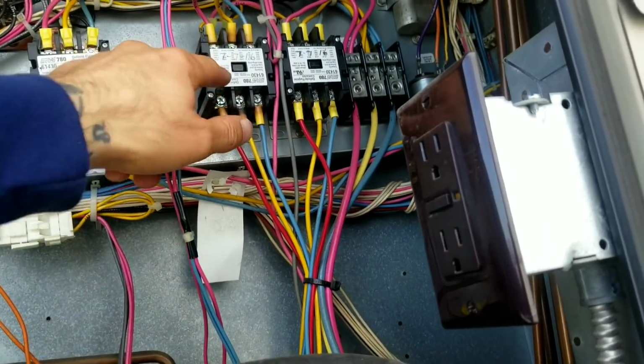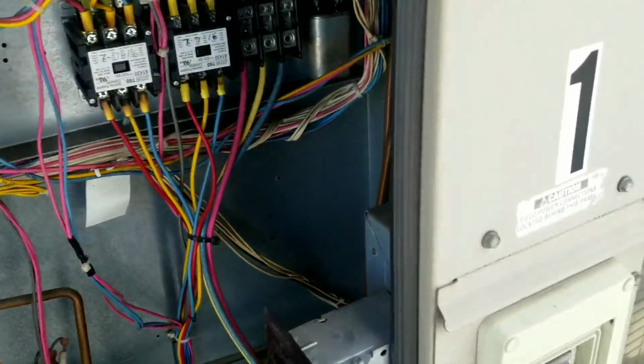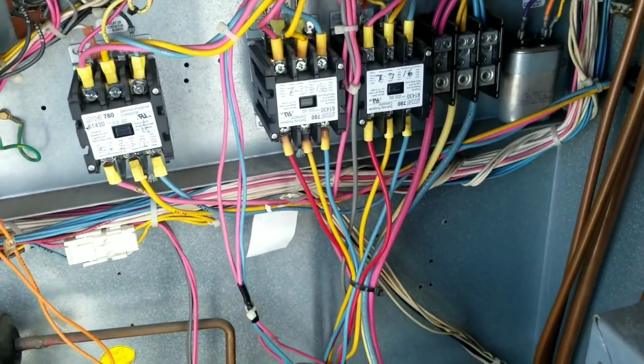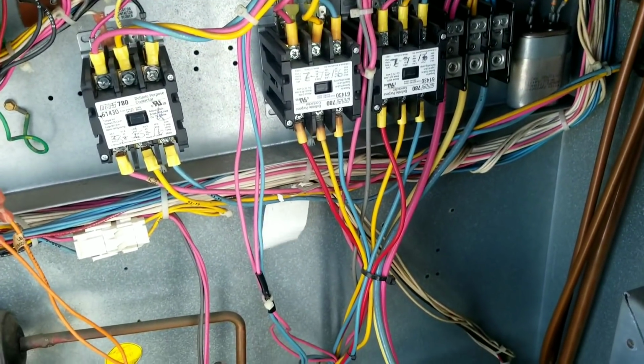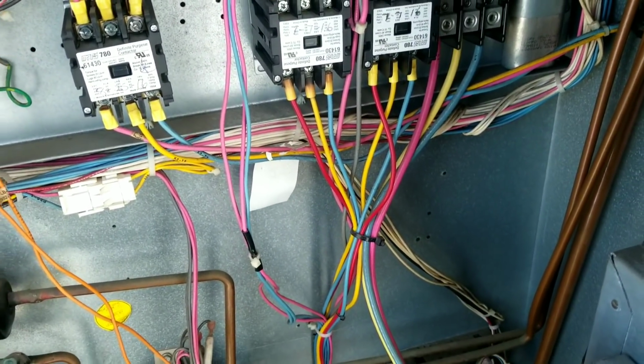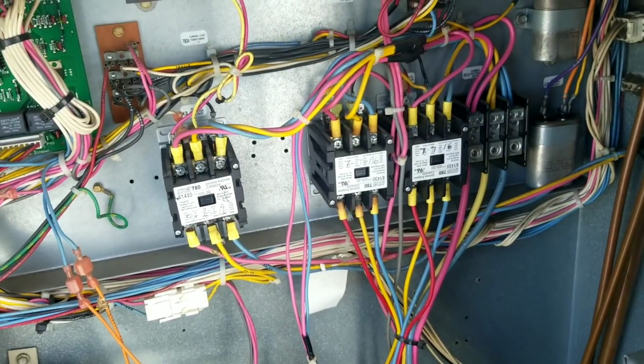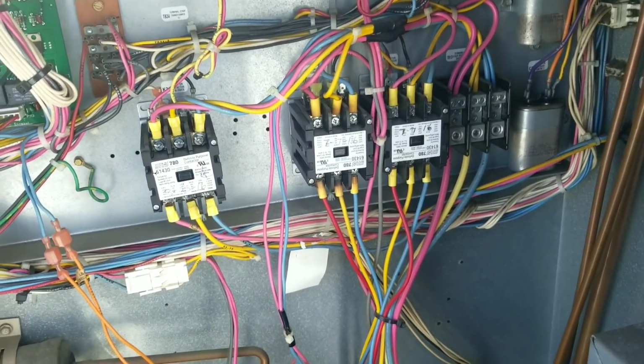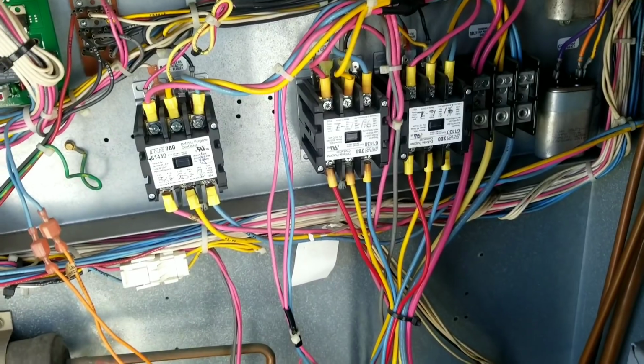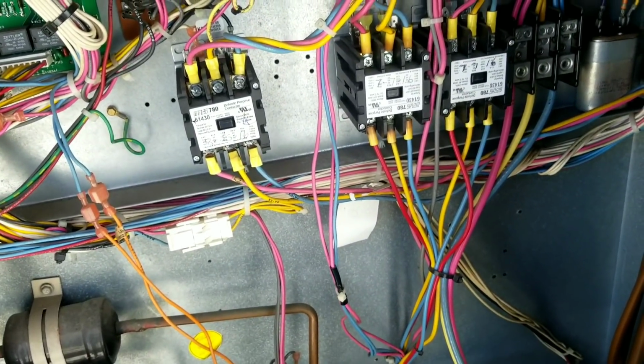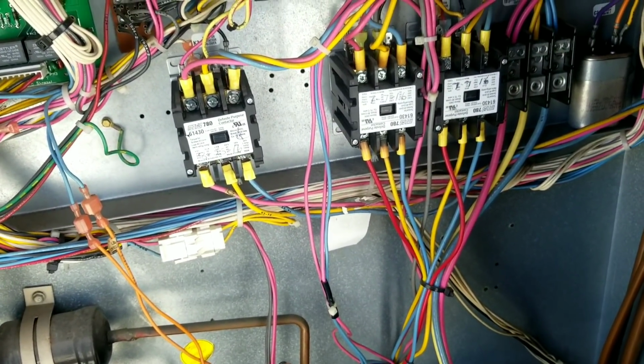Let's open up this cover here. Let's see if the contact points in that contactor are heavily pitted. That is a compressor contactor, so it shouldn't really affect anything to do with the heat.